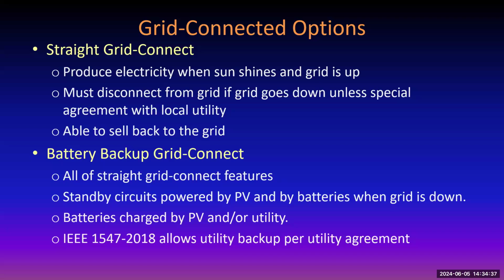And the most recent version of IEEE 1547-2018 says that it is possible for an owner of a photovoltaic system to sign an agreement with the utility to allow the utility to control their system to buy electricity during utility peak time, when the utility maybe needs it. And furthermore, if you've got battery backup, then not only can you sell your electricity to the utility at peak time, but you can buy it from the utility when they have excess, like when the nukes are running at night. If you buy that excess electricity, then they don't have to throttle back their other generation. So some really interesting stuff going on these days, the bottom line. And like I say, a lot of it involves software and communication and other things, and yeah, it requires special purpose hardware, of course, and they're able to do that.